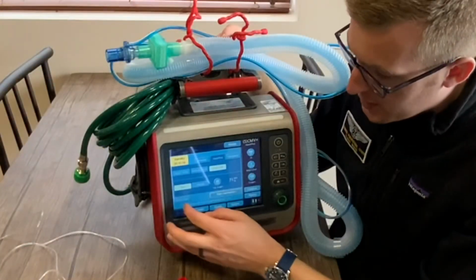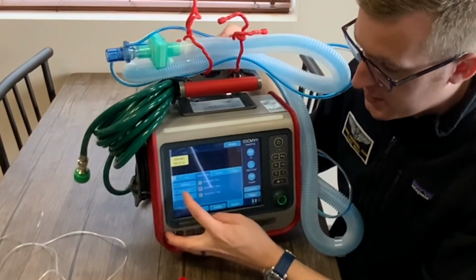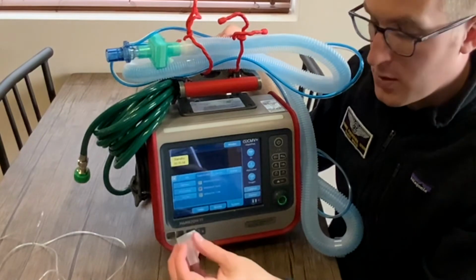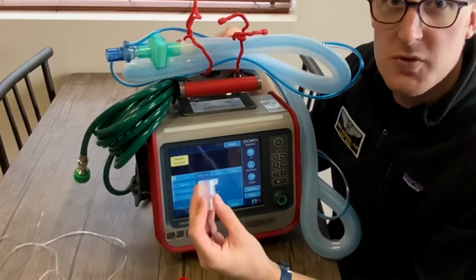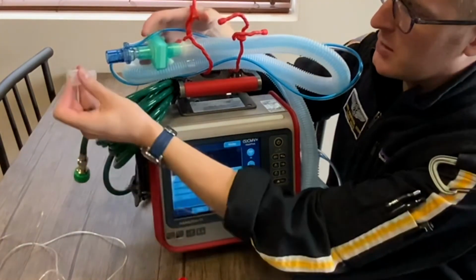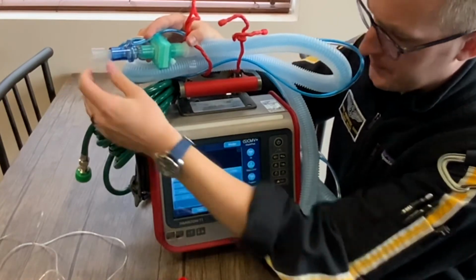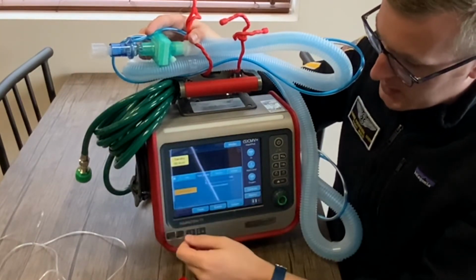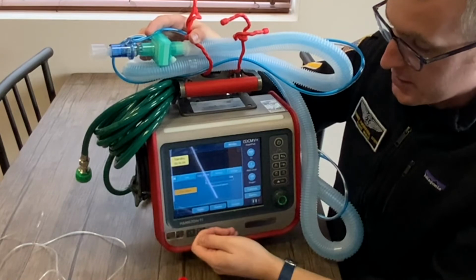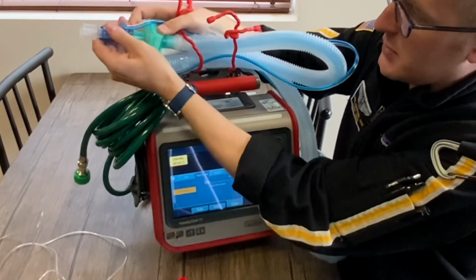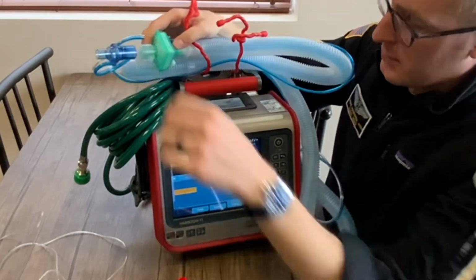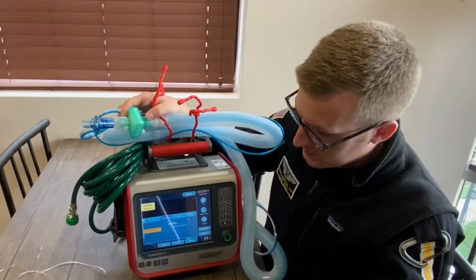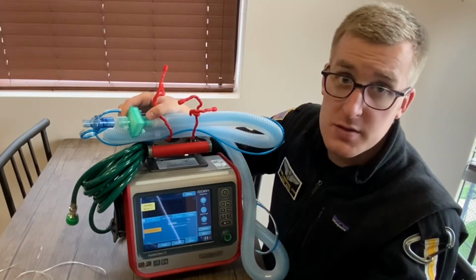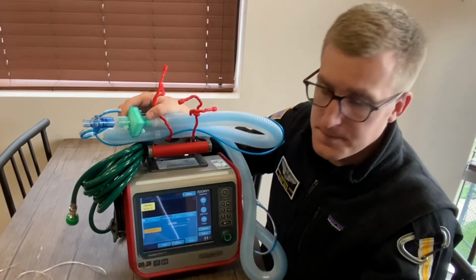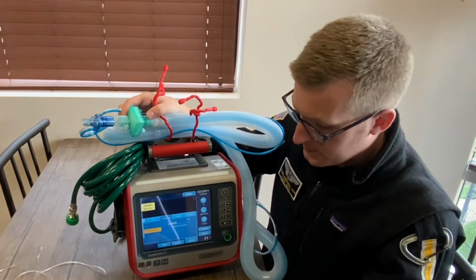The next test we're going to do is the flow sensor test. In order to do so, we use the dongle that comes with the new set of tubing. Insert the dongle into the flow sensor, hit flow sensor to begin the test. Follow the instructions on the screen. Turn flow sensor. It'll say maneuver in progress and slowly ramp up the flow.